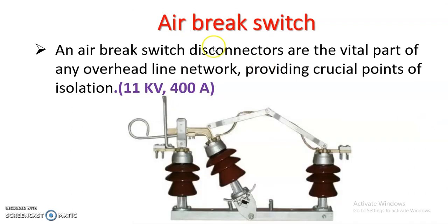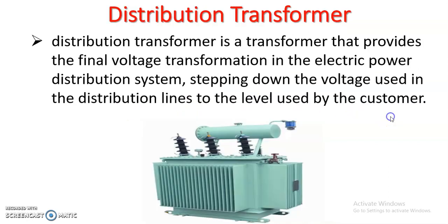Then the next equipment is the air break switch. It is a simple disconnector switch which provides a crucial point of isolation. It will provide the isolation. The rating of this air break switch in case of a plinth mounted substation is 11 kV and the current rating is 400 ampere.